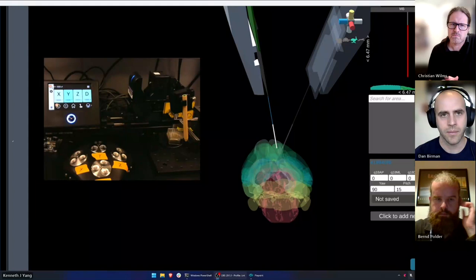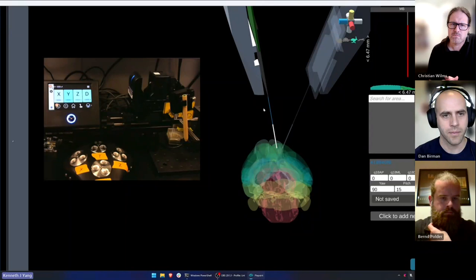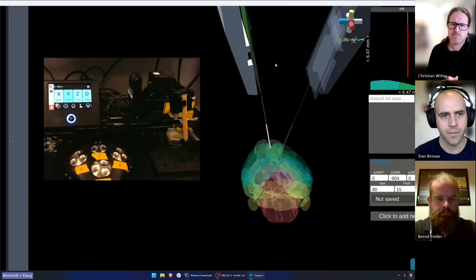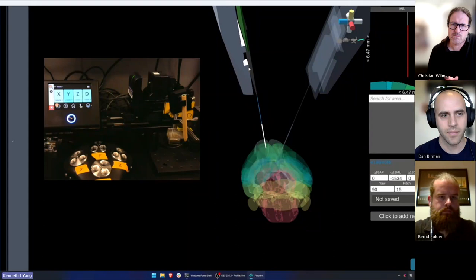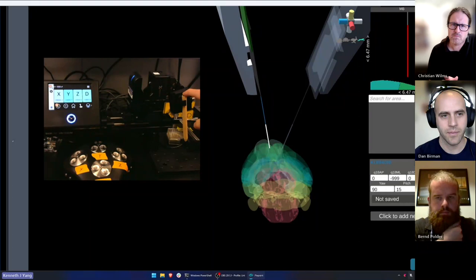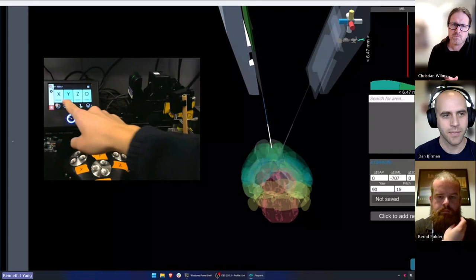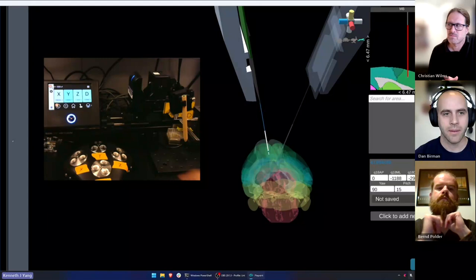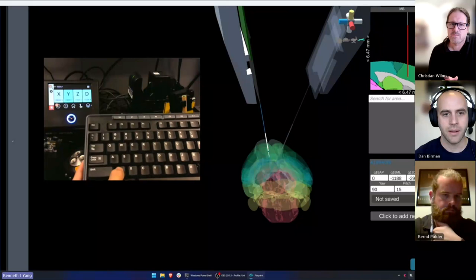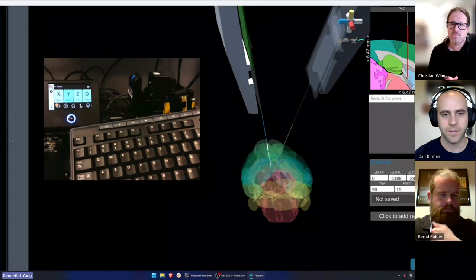With probe number six selected, I can use the WASD keys to move the probes around. I'm hitting the A key right now, and you'll notice how the probe is moving — it's moving at 1,000-micron increments. You can also look at the touchscreen controller and notice how the position is changing. You can use this to navigate around your scene. Also, if you're working with a scenario where you don't have a rotary encoder, you can use the keyboard. I'm pressing the Z key to drive down on the depth axis, and you can see the channel maps update in real time.